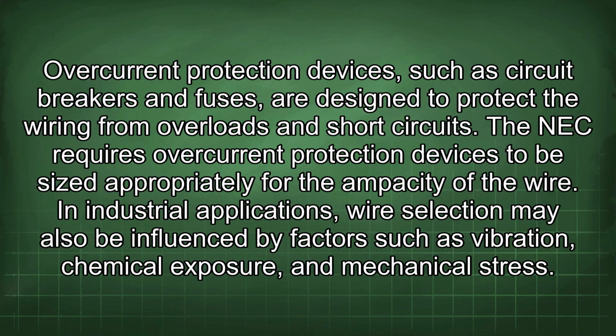Overcurrent protection devices, such as circuit breakers and fuses, are designed to protect the wiring from overloads and short circuits. The NEC requires overcurrent protection devices to be sized appropriately for the ampacity of the wire. In industrial applications, wire selection may also be influenced by factors such as vibration, chemical exposure, and mechanical stress.